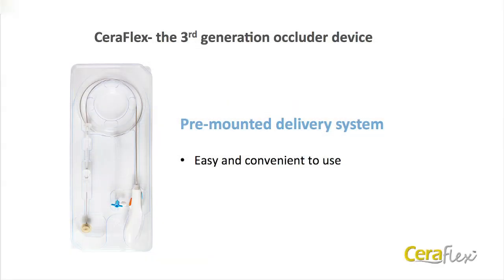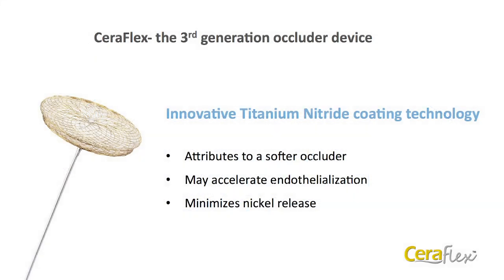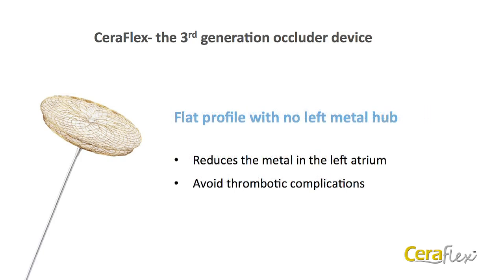The CeraFlex Occluder is a pre-mounted device. Each occluder is pre-connected to the cable and the loader in the device package. It is a self-expandable double-disk device made of nitinol wire mesh. All metallic structures are plated with proprietary titanium nitride coating technology, which attributes to a softer occluder, aiding maximum flexibility and conformability to the patient's anatomy. Tests have revealed a 93% decrease in nickel release compared to uncoated occluders, which may also help to accelerate endothelialization. The elimination of the distal hub is designed to minimize the amount of material left on the disc and to avoid thrombotic complications.